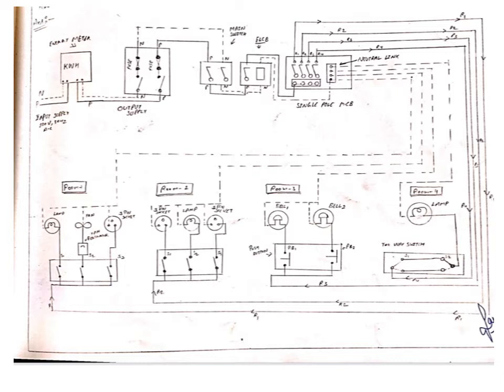Then the output from this main switch will go to the distribution board. On this distribution board, we have connected one two-pole MCB, that is for phase and neutral. Both are controlled by this MCB. As you can see, phase and neutral go into this switch, and then phase and neutral come out as output. So this is a two-pole MCB.